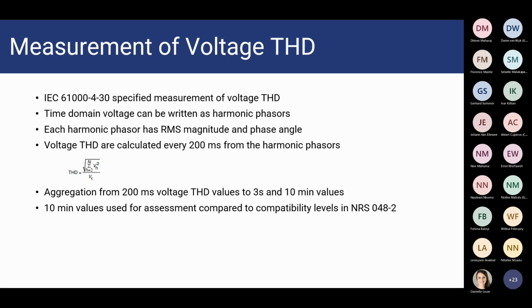Yeah, so Randolph, we have a question here from one of my colleagues. Yes. So, Hein, just a thing to note here, your third bullet where you say harmonic phasors have RMS magnitude and phase angle. Just look at the formula as well for our audience. The THD formula only considers the voltage magnitude and not the phase angle. So although THD is a useful measure to compare against, it really only summarizes the magnitude side of it, showing you half of the picture.